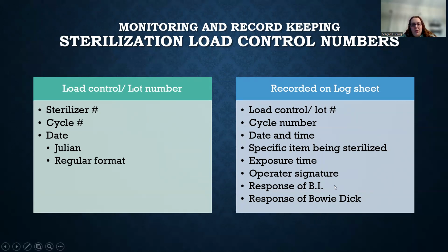You're going to record the response of the BI, which is the biological indicator, and the response of the Bowie-Dick test or the DART test, daily air removal test. It should be done daily.